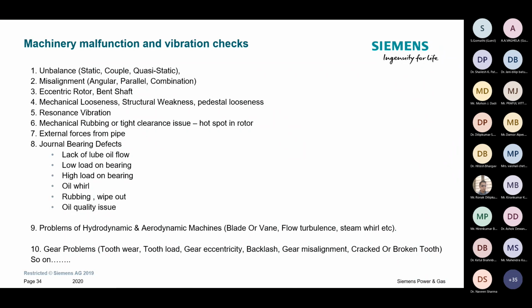So you can imagine it's a big rotor train rotating at 3000 RPM, and the rotors are coupled with bolts. So how accurately do they have to align? We are talking about microns. If they are off by certain microns, then you will see resonance or unbalanced force there.